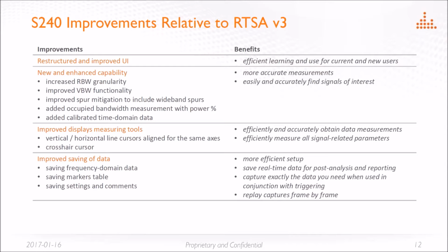Actually, while we're still on this, and we're talking about both the hardware and the software, there's also a question about how we ensure amplitude accuracy. There are a couple of aspects to that, and one of them is that we calibrate our products in our factory over 4 different amplitude settings, as well as over temperature. In addition to that, we also provide NIST traceable calibration, and our spec for the R5500 is plus or minus 1 dB amplitude accuracy.